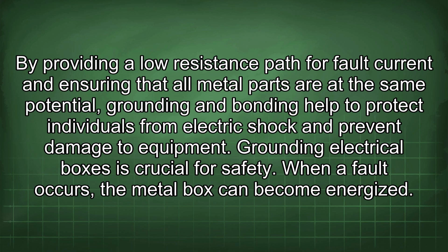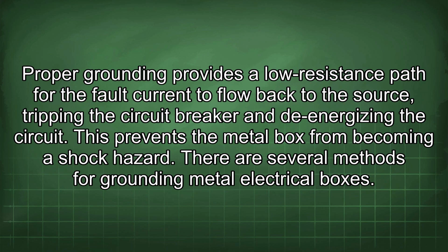Grounding electrical boxes is crucial for safety. When a fault occurs, the metal box can become energized. Proper grounding provides a low resistance path for the fault current to flow back to the source, tripping the circuit breaker and de-energizing the circuit. This prevents the metal box from becoming a shock hazard. There are several methods for grounding metal electrical boxes.